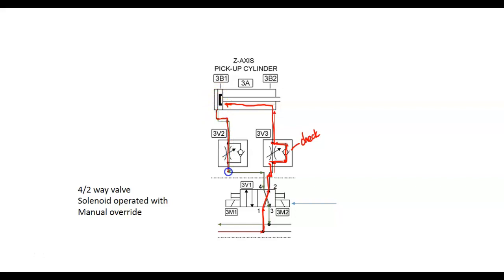So now what we're doing is running it through what we call a flow control valve. This is what we use to control the speed. If you control it on the output, on the exhaust side, we refer to that as meter out. In pneumatics or hydraulics, it doesn't make a difference, but in pneumatics we need to meter out, because if you meter in, as soon as it moves, the air uncompresses and then has to recompress. So what we're doing is pushing against something like this.